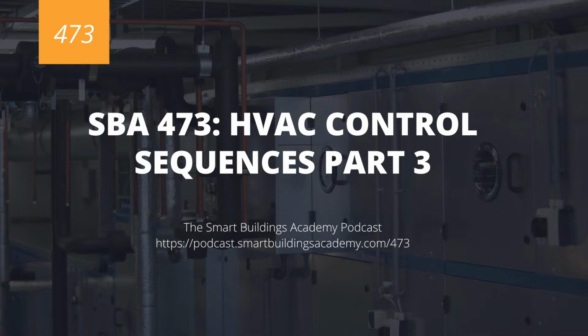We essentially are doing a demand-based reset. That's what it's called. Now, we utilize this because when we're using constant air volume systems, we're not going typically for 55 degrees and hitting saturation and then allowing the air to mix once it actually gets to space. We want to go and provide a constant volume of air, and we are hoping to control discharge air and sometimes even humidity at a constant volume unit. So we're focused in on that.